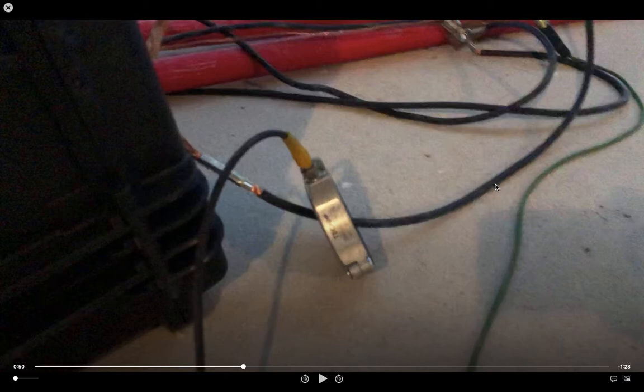The reason we have two of these is simply because we want to have a better picture, better insight, and better context, especially since the capacitive divider is more sensitive. That's why we are connecting the capacitive divider directly - it is physically connected to the cable. But on the other side, indirectly, we connect an HFCT because HFCT, also being very sensitive, gives us something more: it gives us the understanding of directionality. You can understand whether the PD will be coming from this side or from this side.